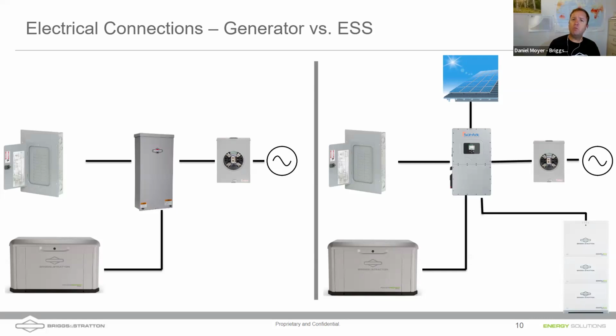When we add a generator into an energy storage system, it's pretty similar, right? We still have our meter can, the meter socket. We're going to have a disconnect in there as well. But now, especially with the advent of much larger, more powerful inverters like the Sol-Ark 15K, that's able to take all 200 amps in from the grid, we're able to use the Sol-Ark as the transfer switch.